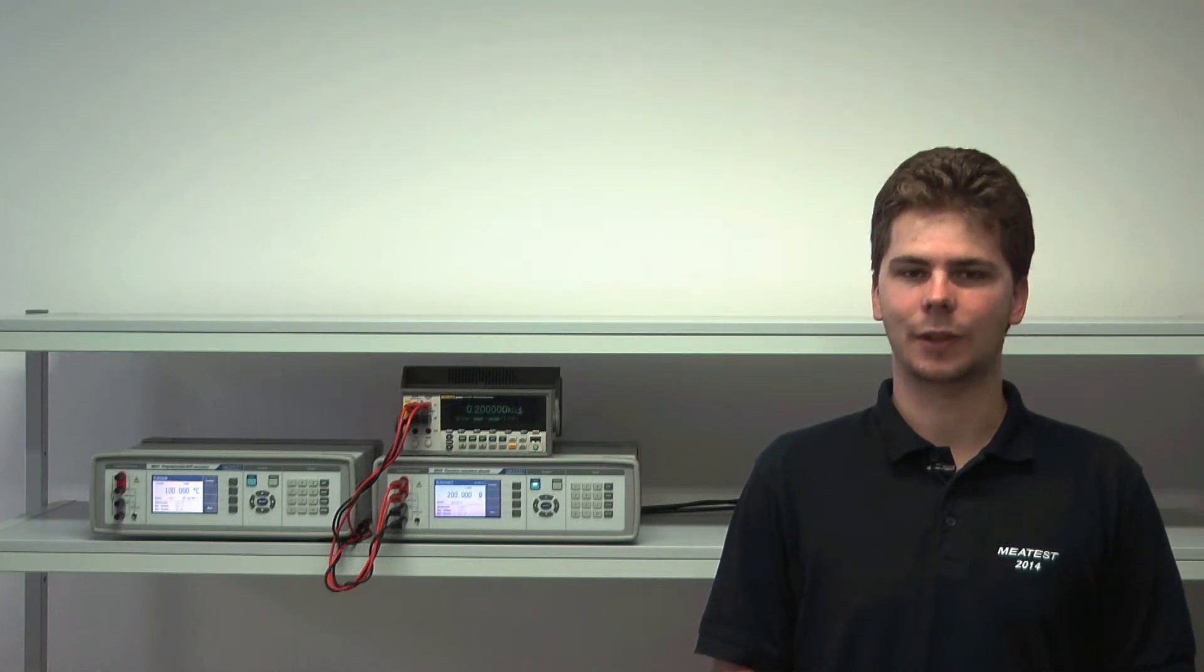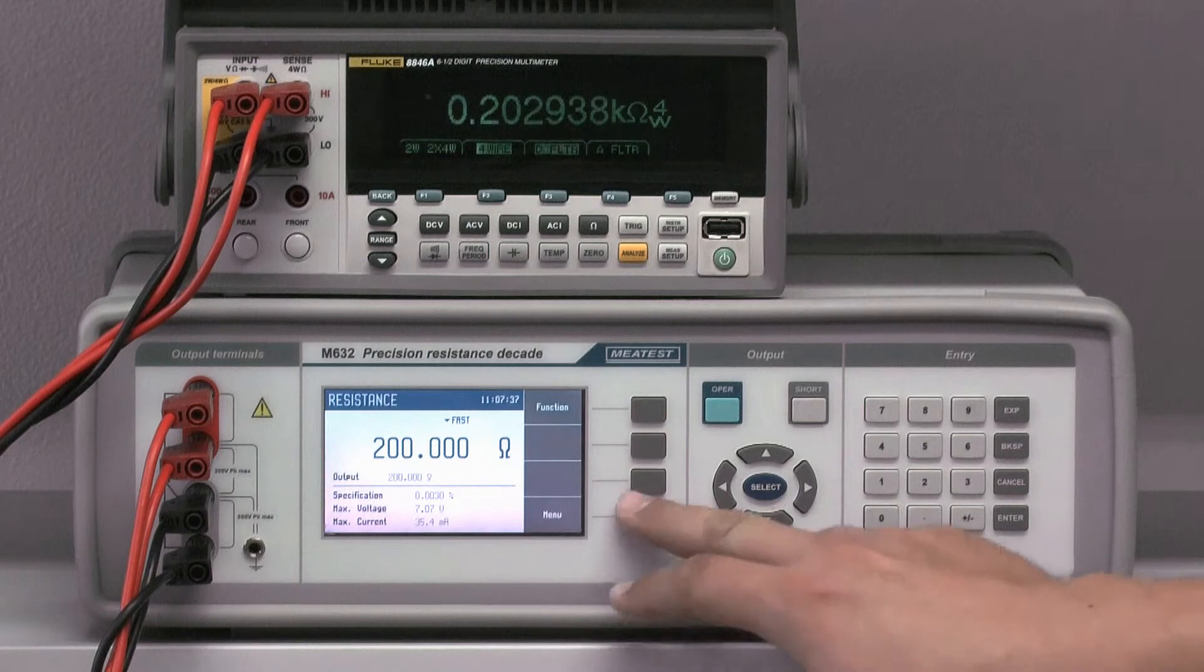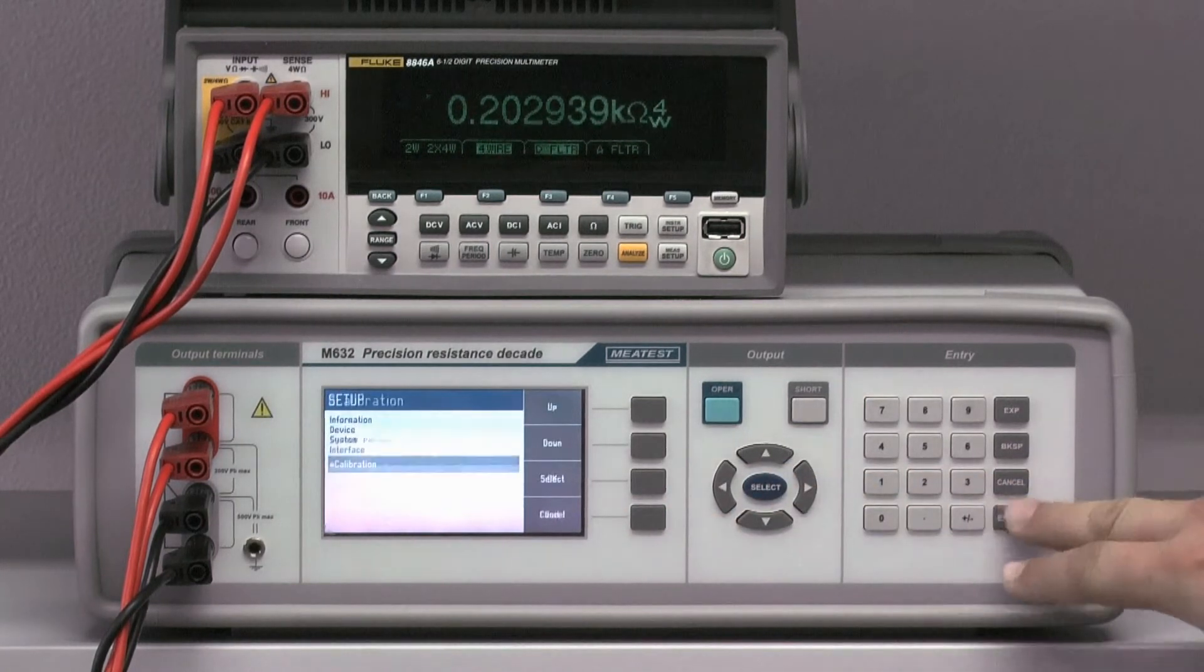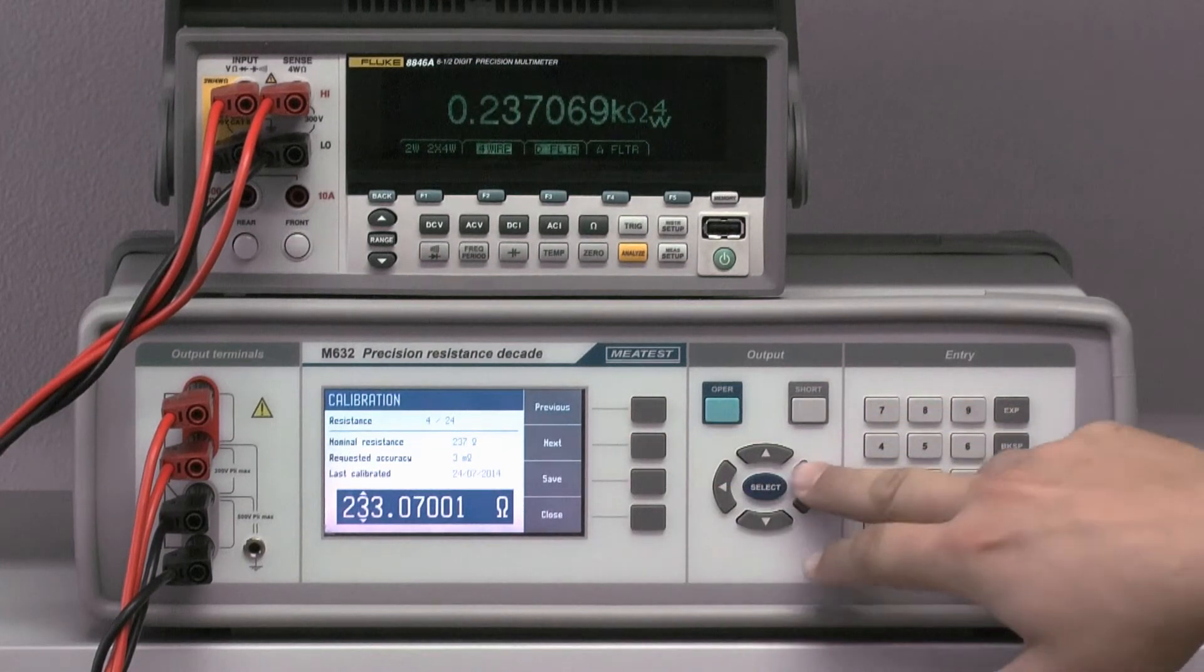Luckily though, this is thing of the past. The M600 series is capable of simple recalibration, a feature completely unknown to other manufacturers. Simply as that, you can adjust values of the internal resistors, restoring it to brand new conditions and thus keeping the costs low.